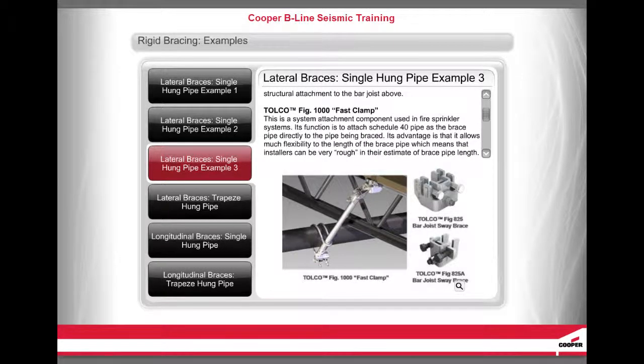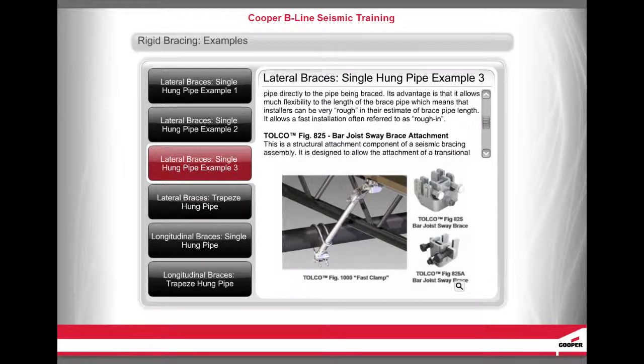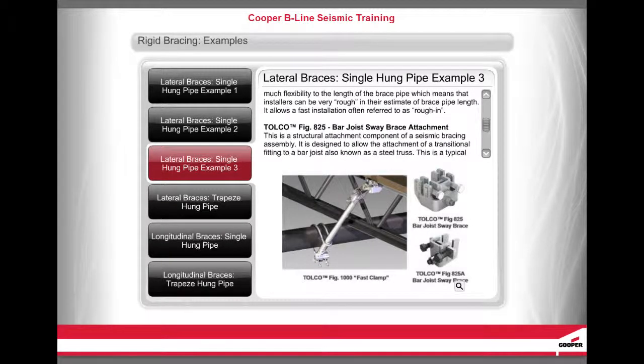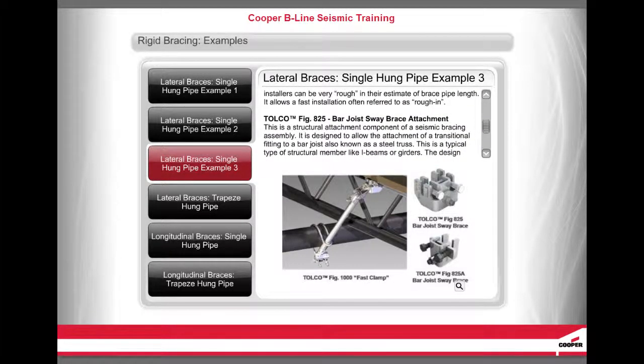The Tolco Figure 1000 Fast Clamp is a system attachment component used in fire sprinkler systems. Its function is to attach Schedule 40 pipe as the brace pipe directly to the pipe being braced. Its advantage is that it allows much flexibility in the length of the brace pipe, meaning installers can be very rough in their estimate of brace pipe length, allowing fast rough-in installation.